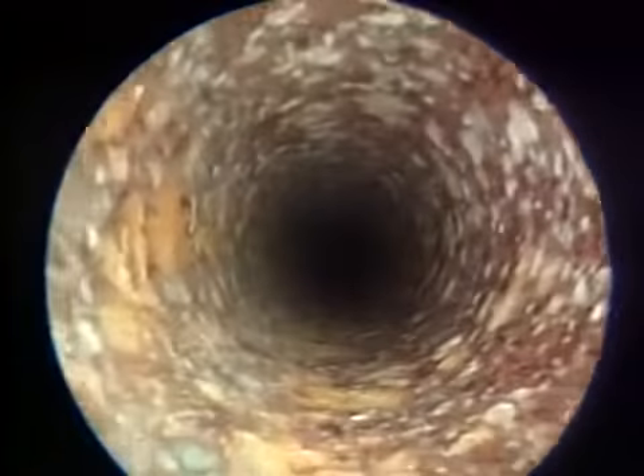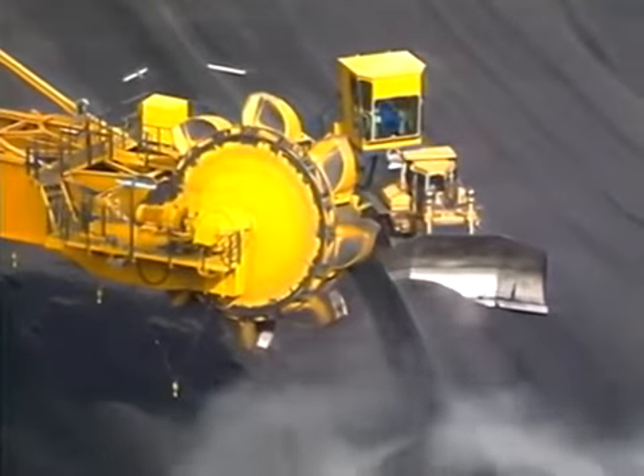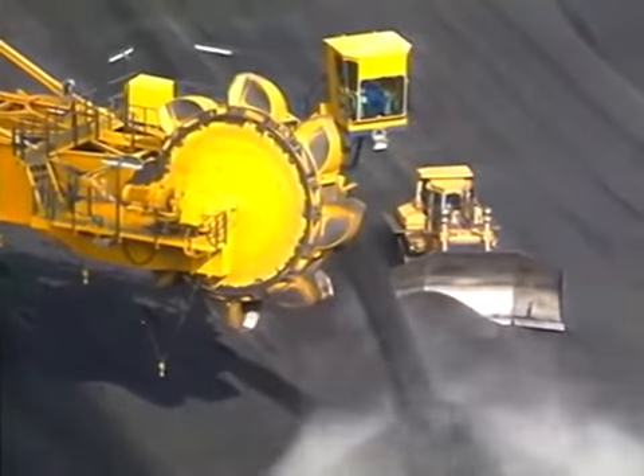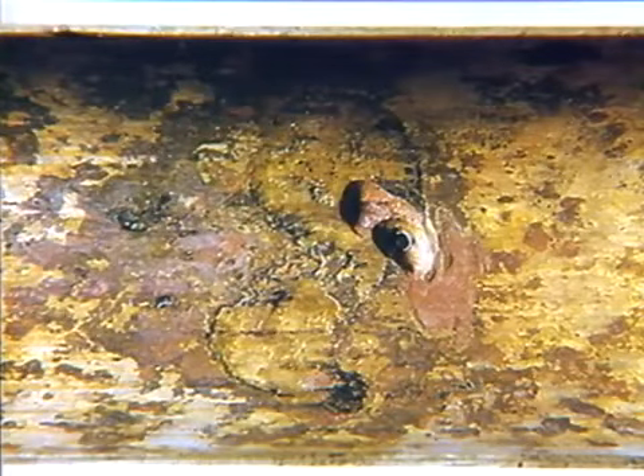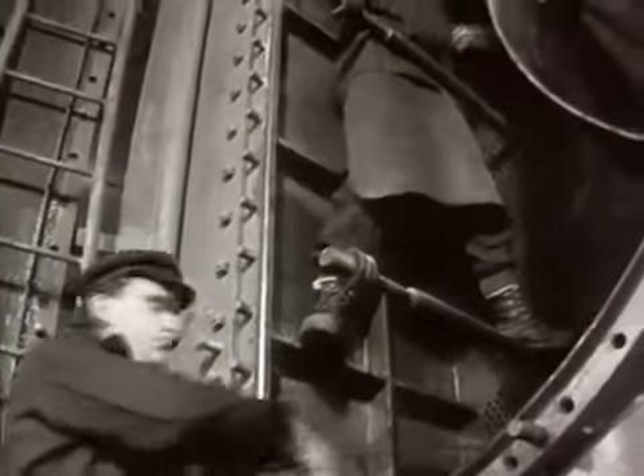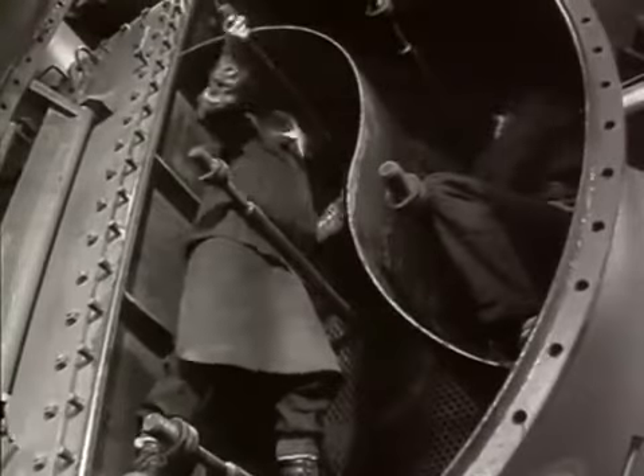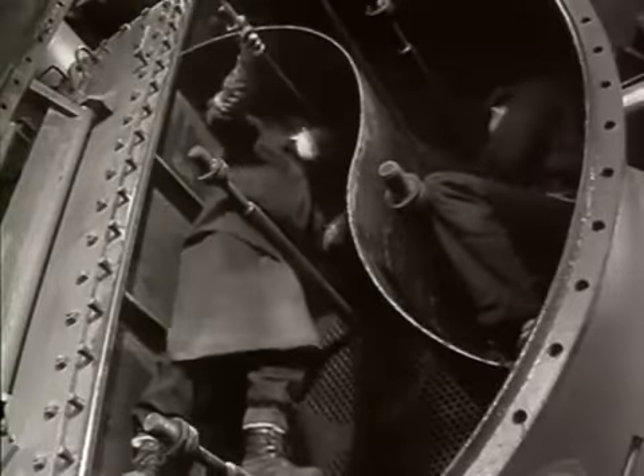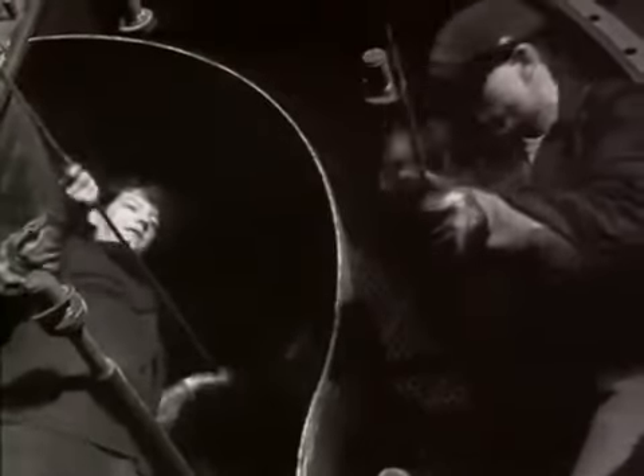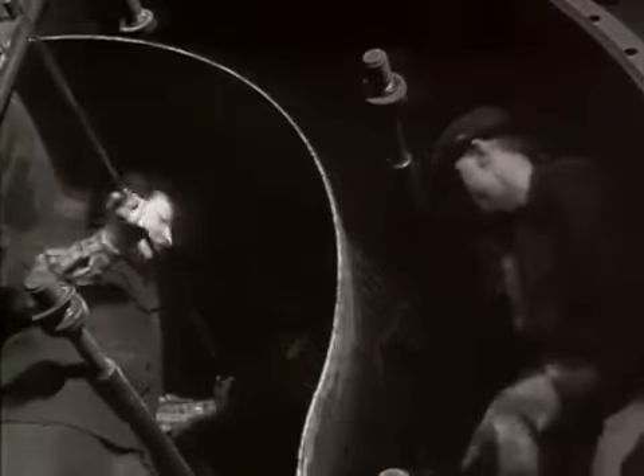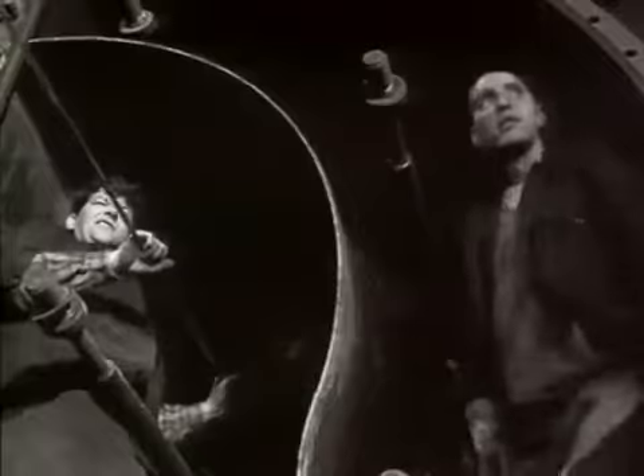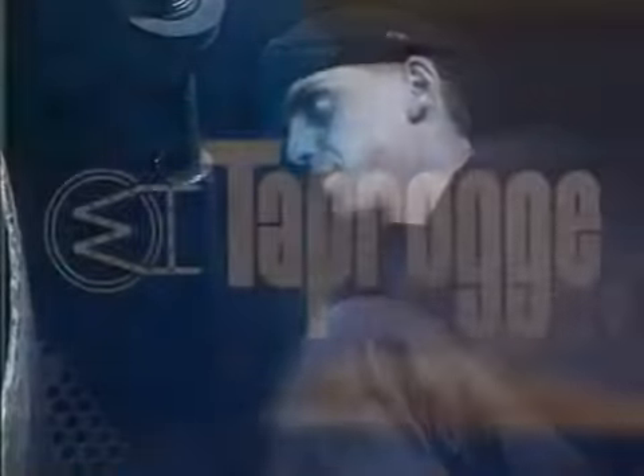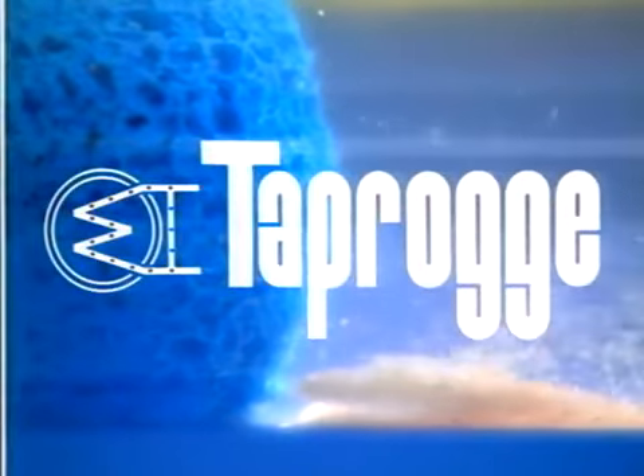Other than fouling, cooling water can cause corrosion, depending on the type of condenser tube material. This leads to increased operating cost by raising fuel consumption with higher pollutant emission and the risk of unscheduled outages from corroded condenser tubes. So, logically, since the quality of the cooling water, as the source of fouling, cannot be changed, the condenser must be cleaned regularly. Either manually, and that means reduction of power station output while opening the condensers, laborious, expensive work that also has to be repeated at regular intervals. Or, much easier, with the Taprogge system.